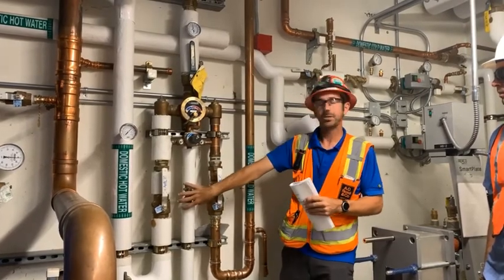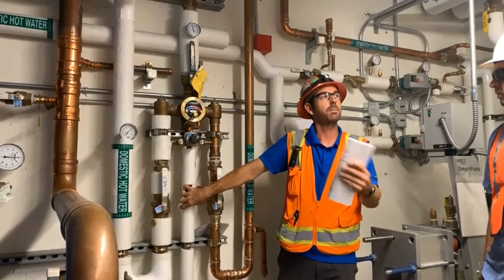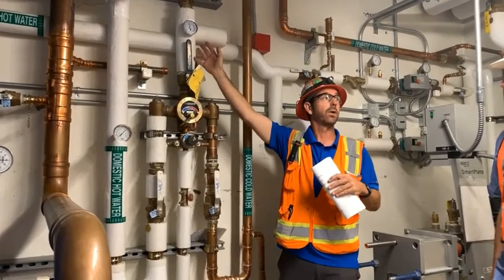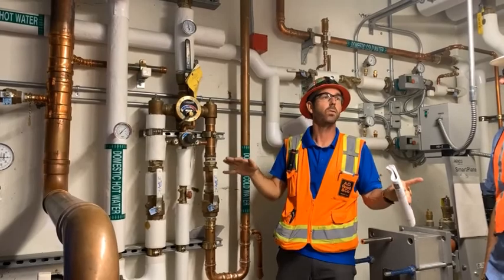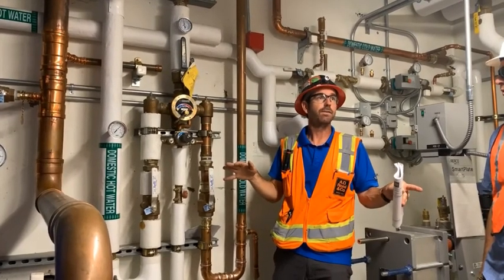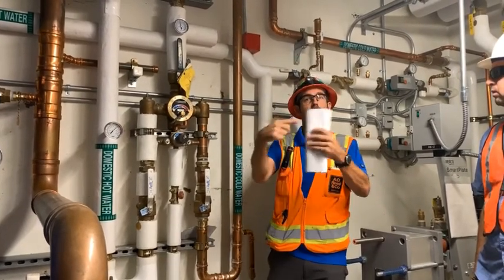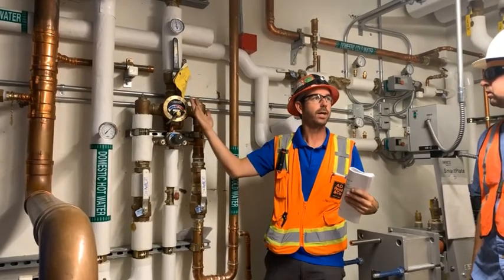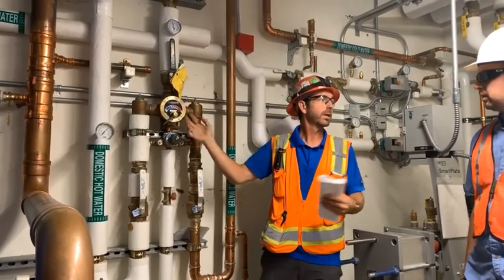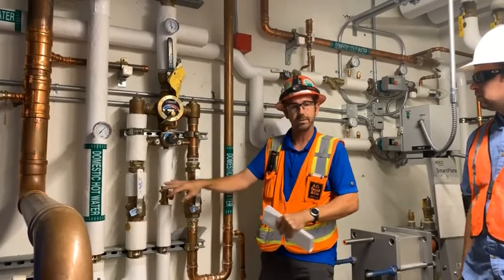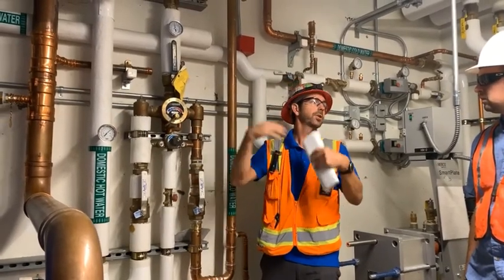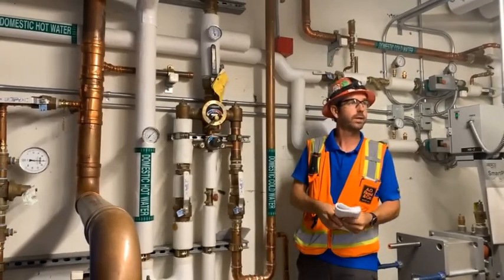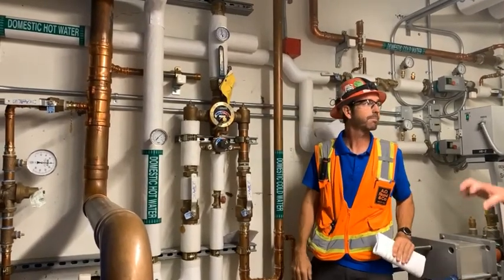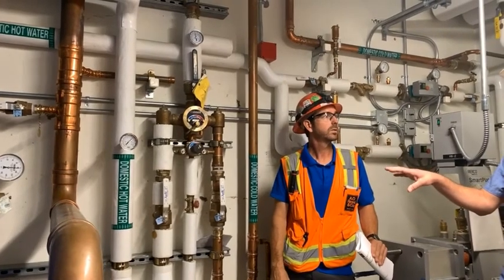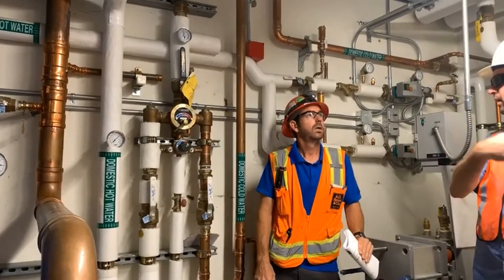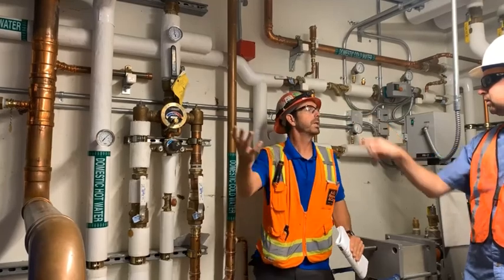So with this return loop that I was talking about, we're relying that it's coming back at 110 to maintain our 120 out in no flow conditions, okay, where nobody's using water. Does that make sense? So if it's cold and you're just trying to rely on that pump to pump it around, but it's only going out at 110, we're never going to be able to heat it up. It's going to take forever. Yeah, because the circuit setters are designed to keep it at 120 when it's returning at 110. So if it's returning at 100 it won't, okay? It'll just take forever. So that's what I'm asking. If it's returning at less than 110, then we should be draining that off instead of letting it come back here? Yeah, you need to bleed it out somewhere.